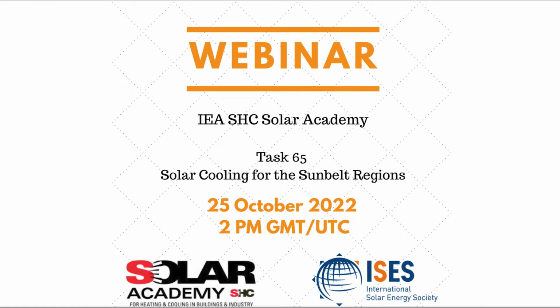For solar thermal collectors, the systems usually involved in solar cooling use either pressurized water, because of its high heating capacity, or direct steam generation. Those are the two main options used today. You can also use thermal oils, but they carry other hazards that aren't environmentally friendly if you get leakages. From both a heating capacity and environmental standpoint, pure water is best. Depending on the application, it's either pressurized water or direct steam, especially for industrial applications, where double effect absorption chillers can be run directly on steam, which is also more interesting from an energy efficiency and COP point of view.